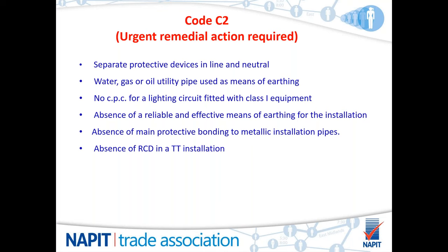Such things are the separate protective devices in line and neutral. Losing the neutral would obviously give rise to people touching equipment that could still remain live. Water, gas, oil utility pipe tube being used as the main earthing conductor, which again is not part of the regulations, and they forbid it. No CPC for the lighting circuit that has Class 1 equipment fitted. The Class 1 equipment will still work, no problem.